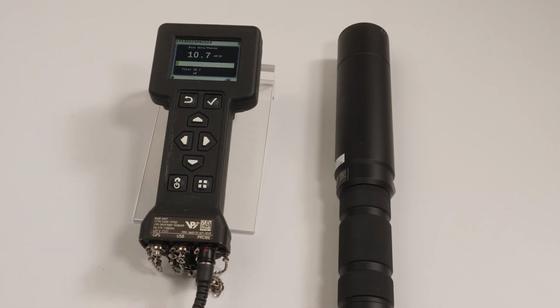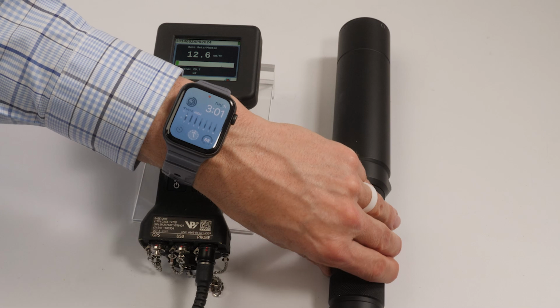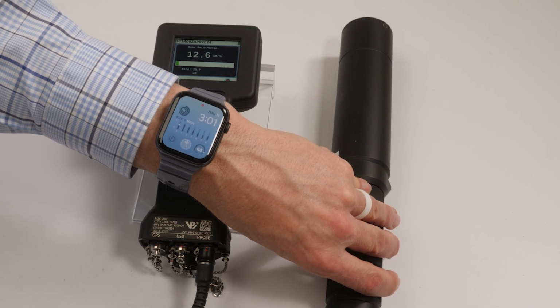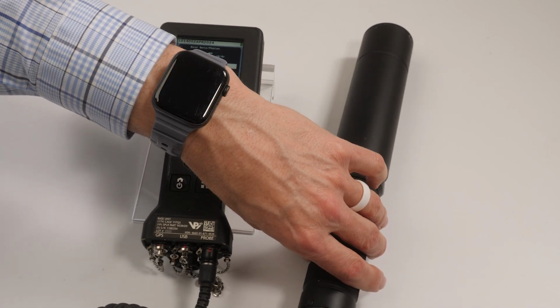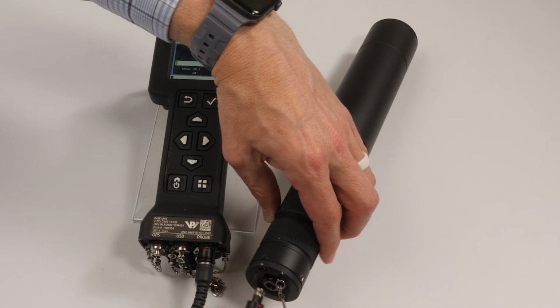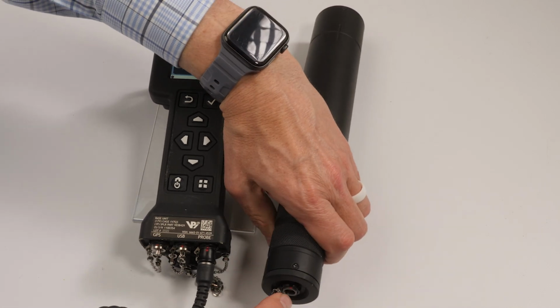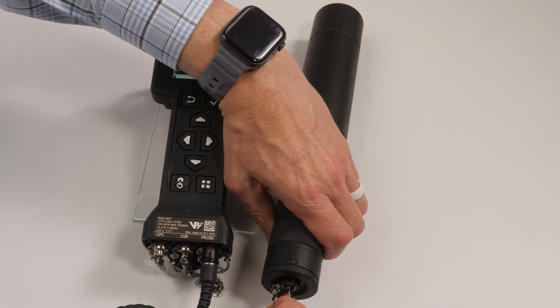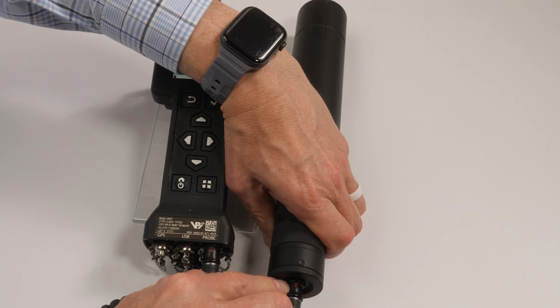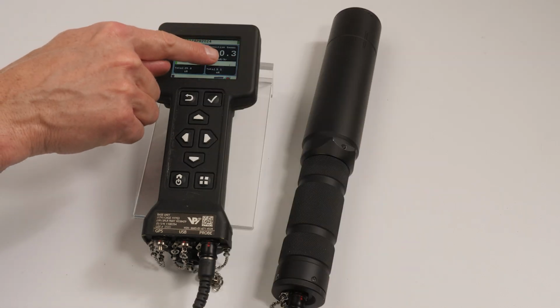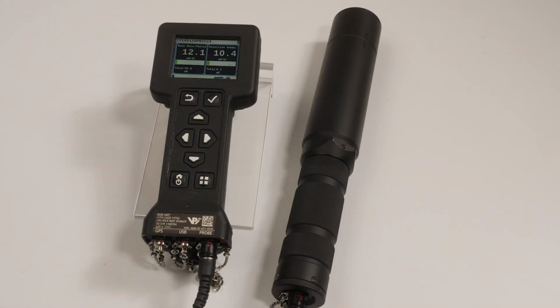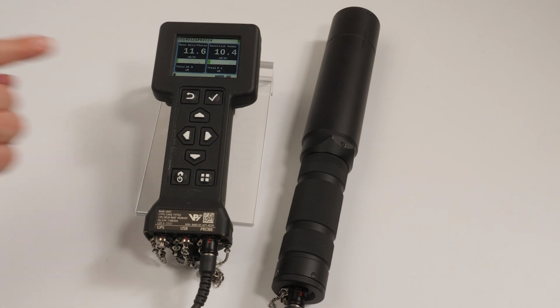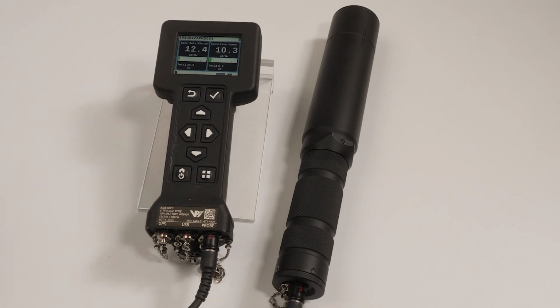Remove the protective cap from the probe. Connect the common probe cable to the probe by aligning the red dot on the probe's connector to the red dot on the end of the common probe cable collar. Insert until the connector is fully seated. Verify that the base unit home screen displays the sensitive gamma radiation reading panel and the probe icon shows on the footer. Also verify that the correct units of measurement align with the requirements of your survey or mission.